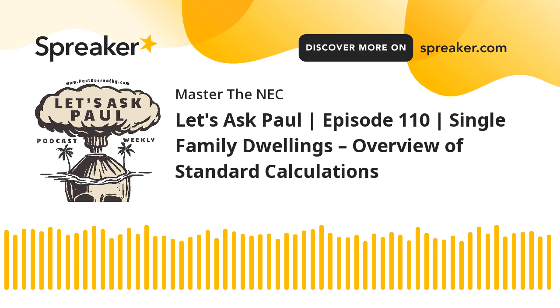So if you go down and look at 220.42, before you even look at the table, just look at 220.42. Here's what it says. It says the demand factors specified in Table 220.42 shall apply to that portion of the total branch circuit load calculated for general illumination. They shall not be applied in determining the number of branch circuits for general illumination. That's not what we're doing here. We're doing a load calc. So we're not doing that in order to try to determine how many branch circuits we need. We're doing a load calc, and so this gives us permission to apply this table.